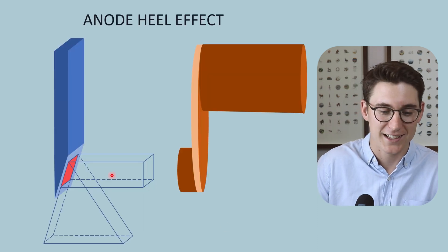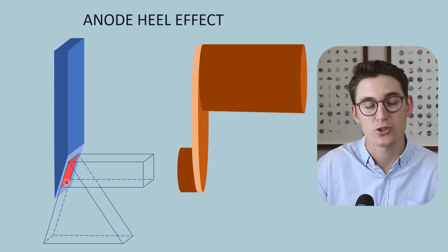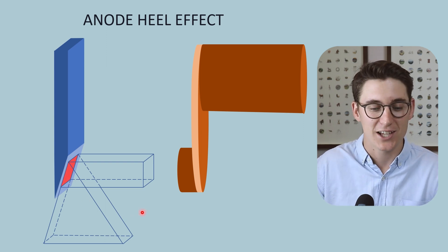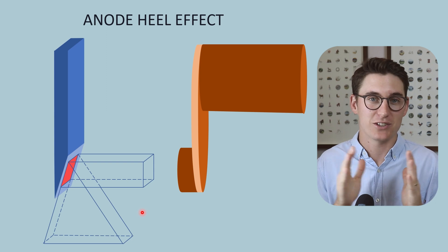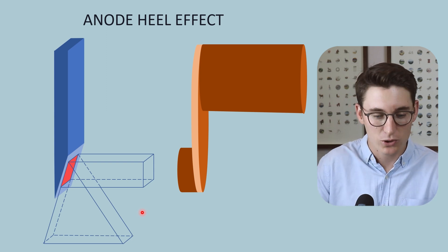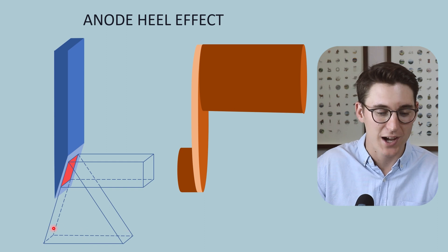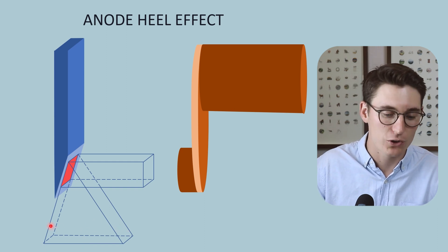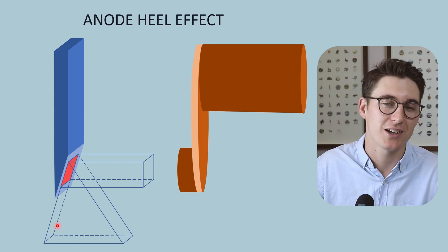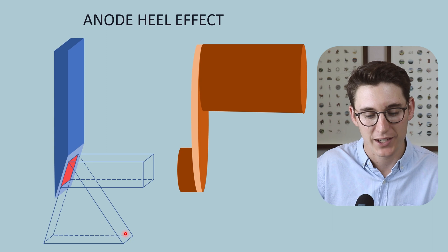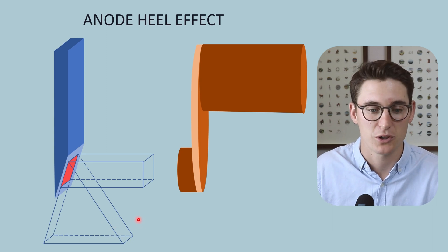Now in the last talk we looked at the focal spot and we saw that reducing the anode angle reduced our field size as well as reduced our effective focal spot size. We also saw that our effective focal spot size actually changes throughout our field. The closer we get to the anode side we get a smaller effective focal spot and as we move out towards our cathode side we get a bigger effective focal spot.